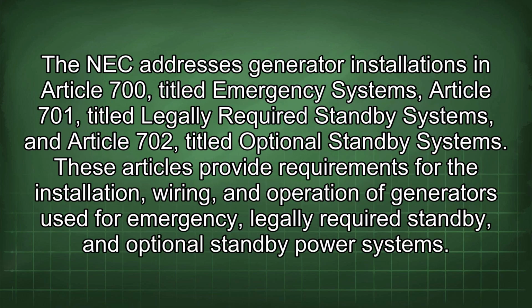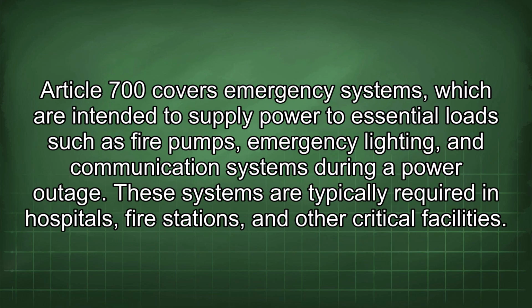codes. The NEC addresses generator installations in Article 700 titled Emergency Systems, Article 701 titled Legally Required Standby Systems, and Article 702 titled Optional Standby Systems. These articles provide requirements for the installation, wiring, and operation of generators used for emergency, legally required standby, and optional standby power systems. Article 700 covers emergency systems, which are intended to supply power to essential loads such as fire pumps, emergency lighting, and communication systems during a power outage. These systems are typically required in hospitals, fire stations, and other critical facilities.